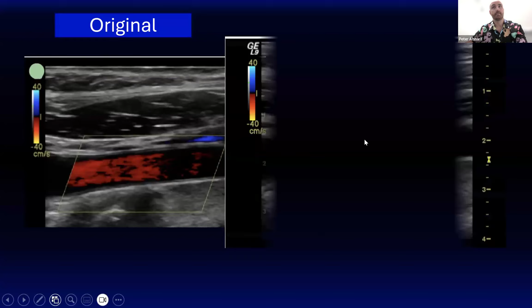So when you have the color box open, you increase the gain and it changes the way that the machine is displaying these flows. It doesn't change anything about how the machine is picking up the flow, but it's just making it show up a little bit better. And so that's the first thing you can do to troubleshoot this, just increase the gain and just see what happens. In this case, we've got a better picture of what the flow looks like.